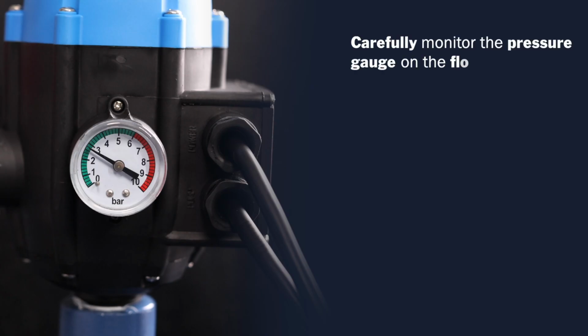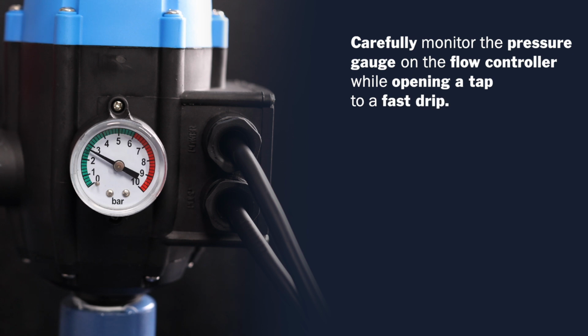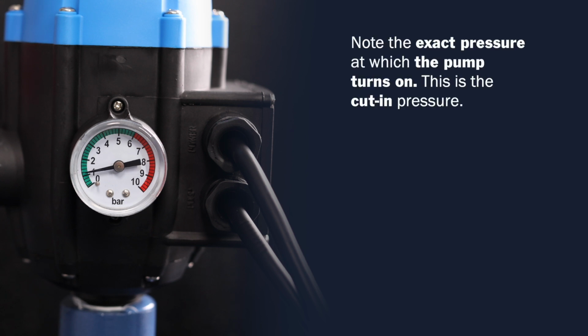Step 7. We will now begin the adjustment for the cut-in pressure. This is the pressure at which the pump turns on when a fixture is opened. Start by carefully monitoring the pressure gauge on the side of the flow controller while opening a tap to a fast drip. Note the exact pressure at which the pump turns on. This is called the cut-in pressure.